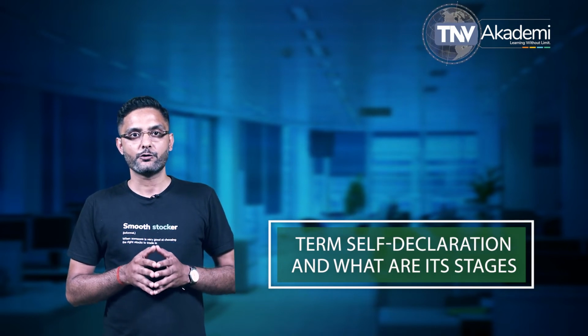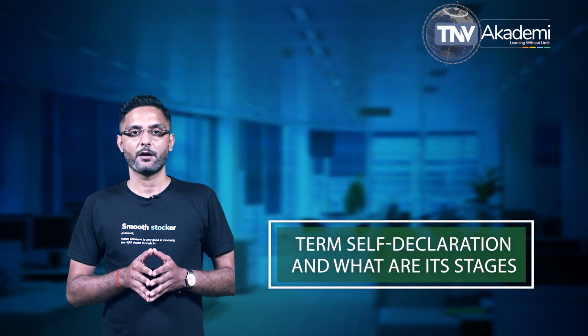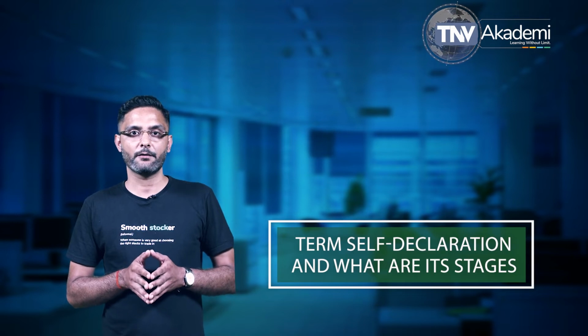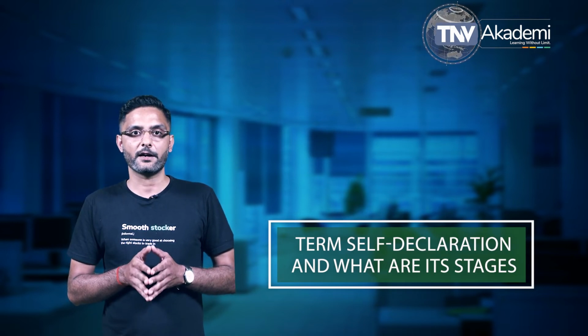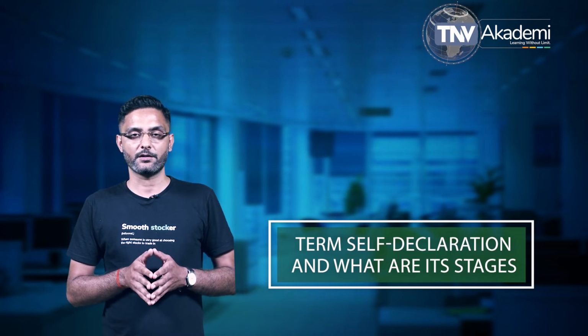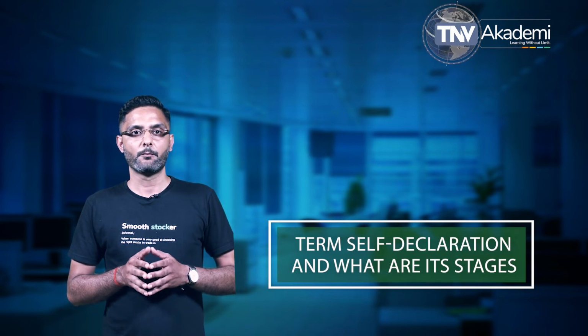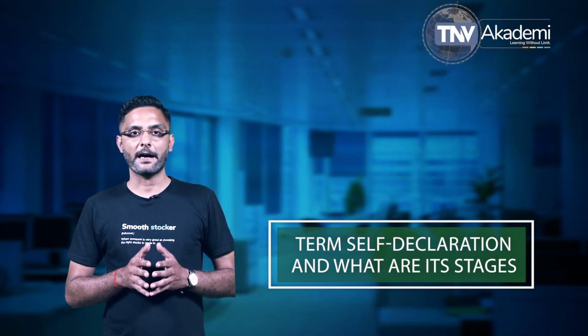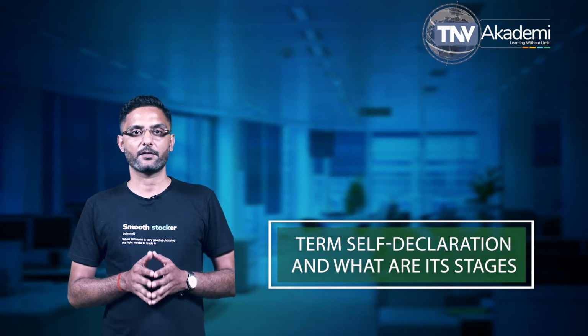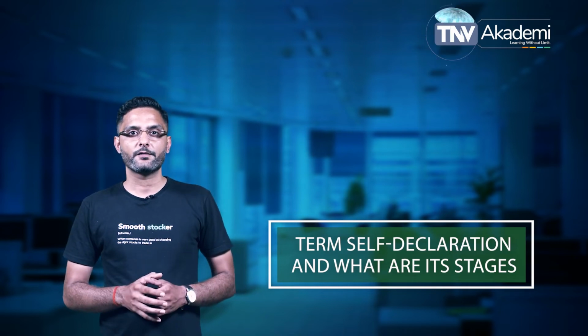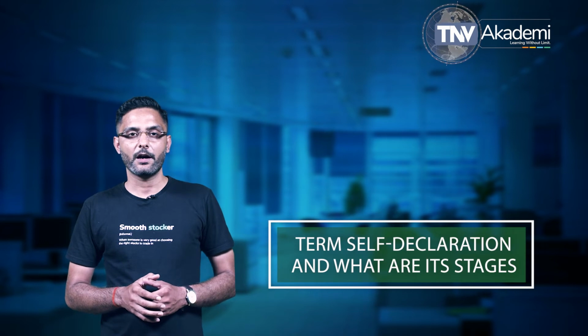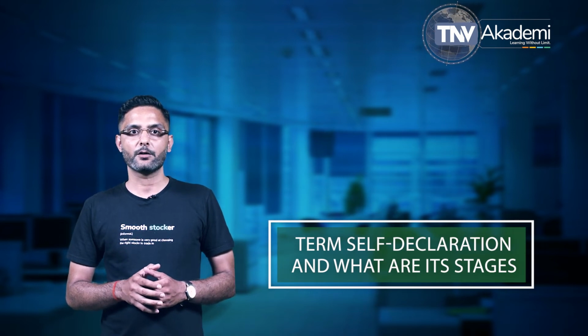The second one, choose the conformity assessment procedure from the modules called out by the directive for the product according to each category involved. There are several modules available for the conformity assessment procedures, but only a few of them involve self-certification. Most of these procedures require a type approval and a production conformity assessment by a notified body.